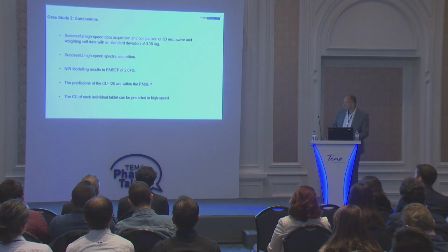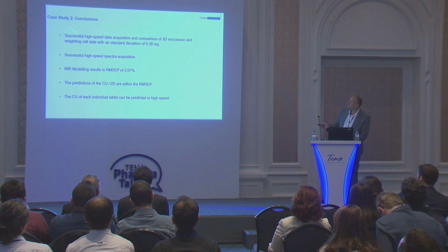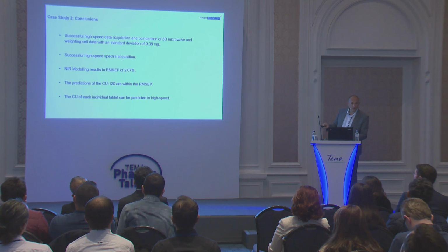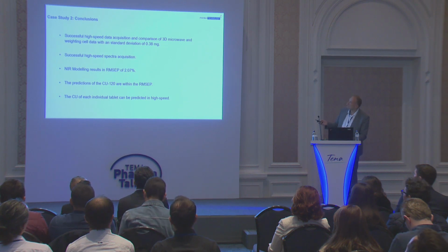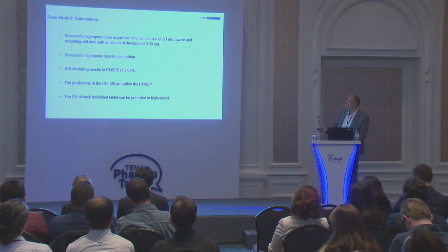Let's also summarize these results here. So we applied successful high-speed data acquisition and a comparison of the 3D microwave and the external scale, the weighing cell data, with a standard deviation of 0.38 milligram. So we are still within the required thresholds.